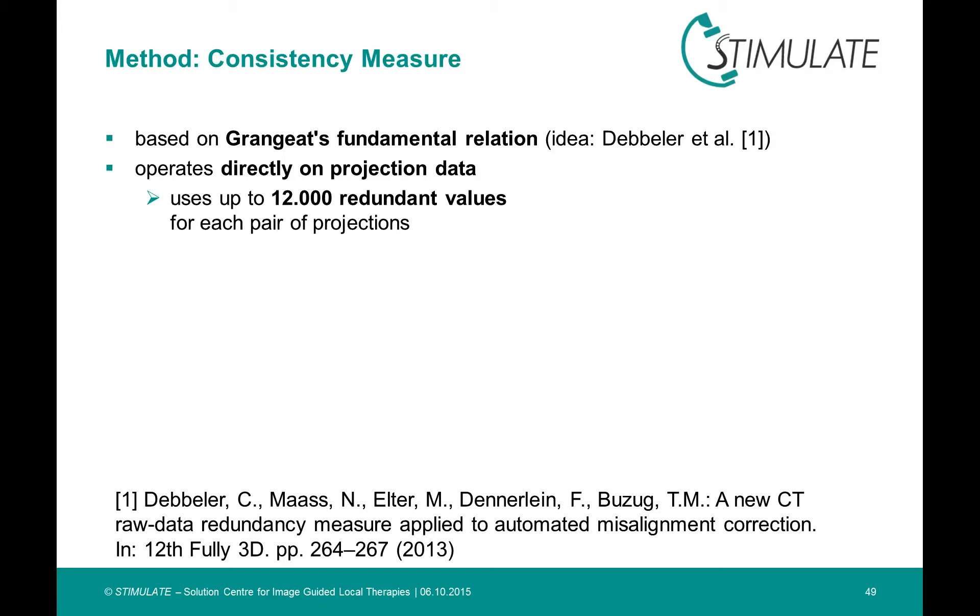It was in connection with the calibration of industrial CT scanners. It works directly on the projection images and has no need for a reconstruction. The advantage of this measure in contrast to other methods which use redundancy is the large number of redundant values you can obtain. We are able to collect up to 12,000 redundant values for each pair of projections.